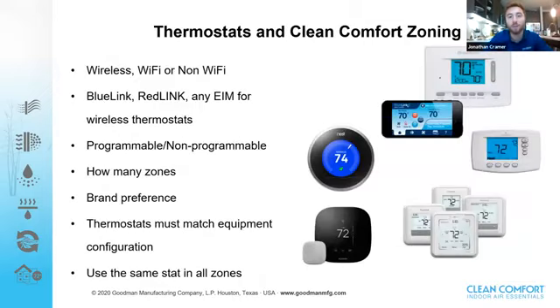What's cool about our Clean Comfort product lines for both our premium and our economy versions is that we accept any thermostat, which is directly in line with what Goodman and Amana are doing right now with the Comfort Bridge product. So with Comfort Bridge, you can use any thermostat, any 24-volt thermostat. Well, same goes for our Clean Comfort. We're trying to put the thermostat and the decisions of that to the homeowner. We're not telling you that if you're going to use our zoning equipment, you then have to go buy a $400 or $500 thermostat. Any 24-volt signal works. So as you see, Ecobee, Nest, Braeburn, Honeywell, all those work perfectly with those.